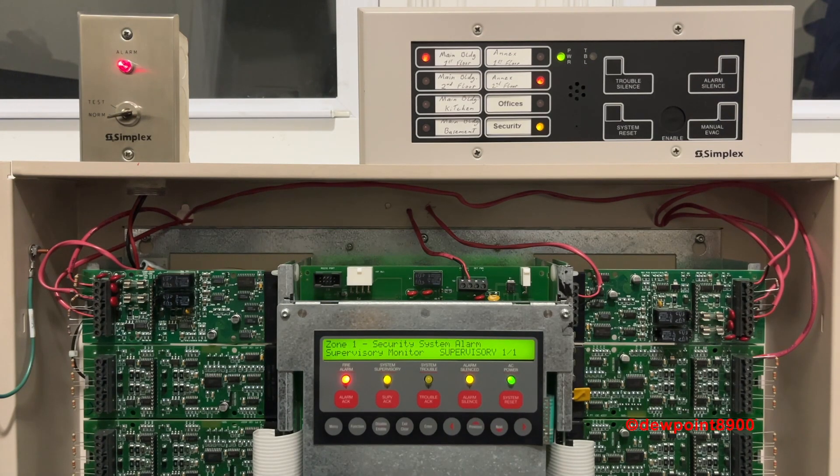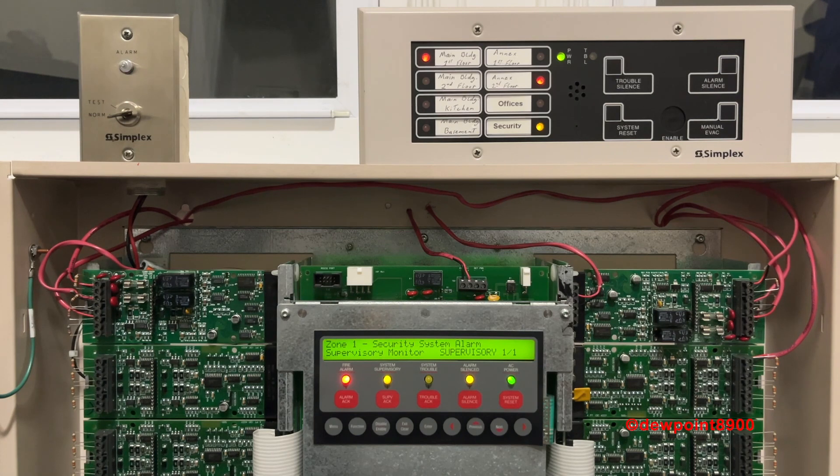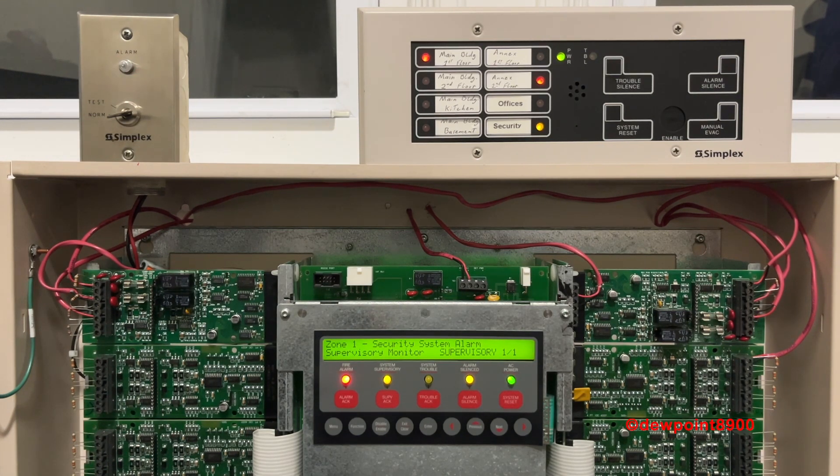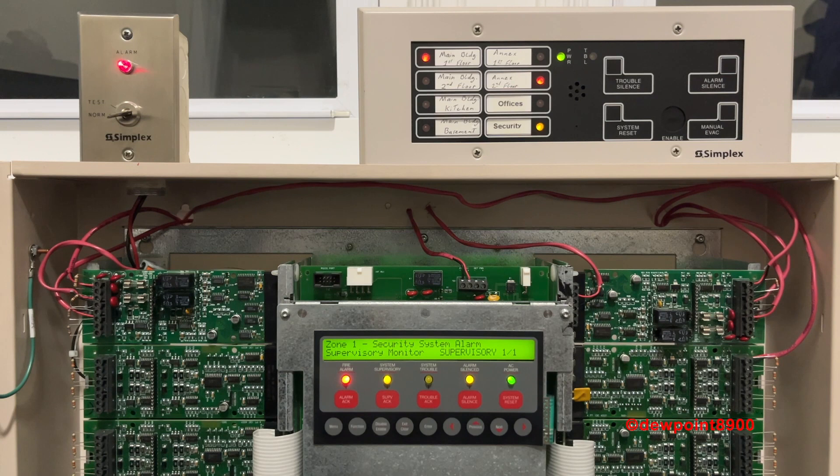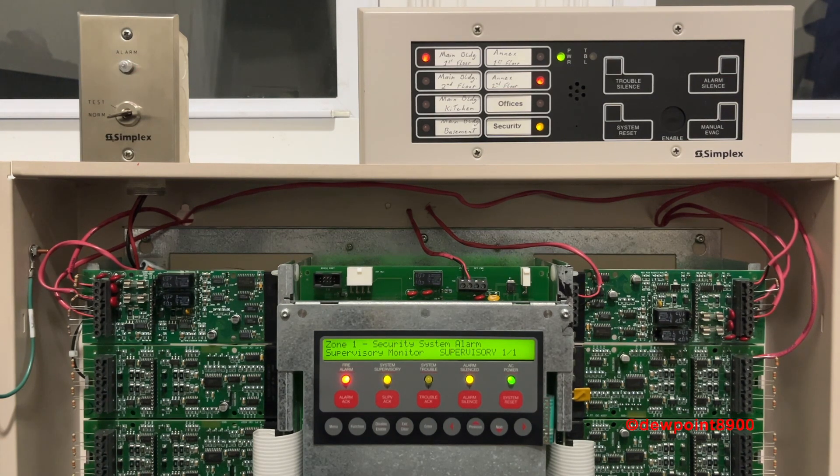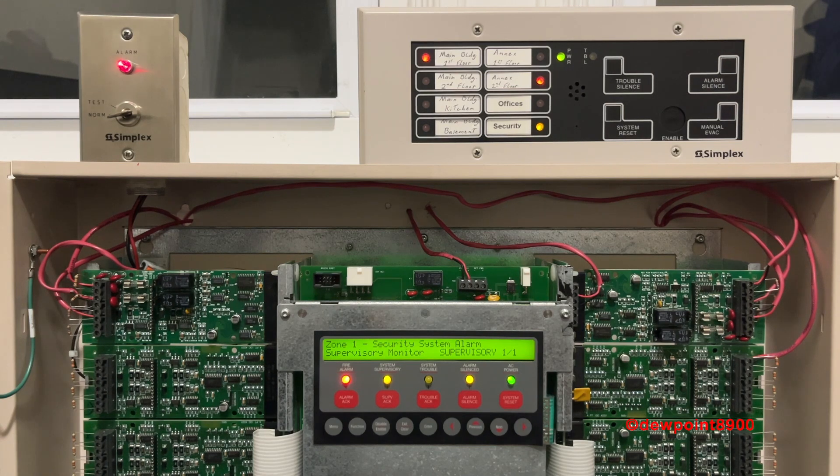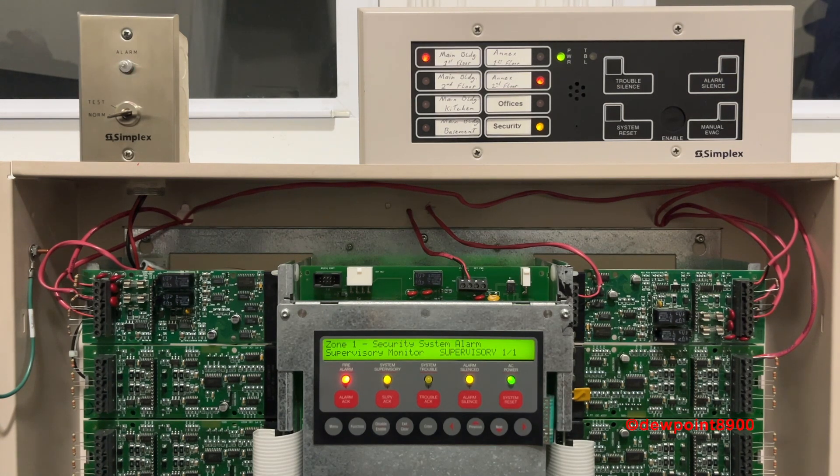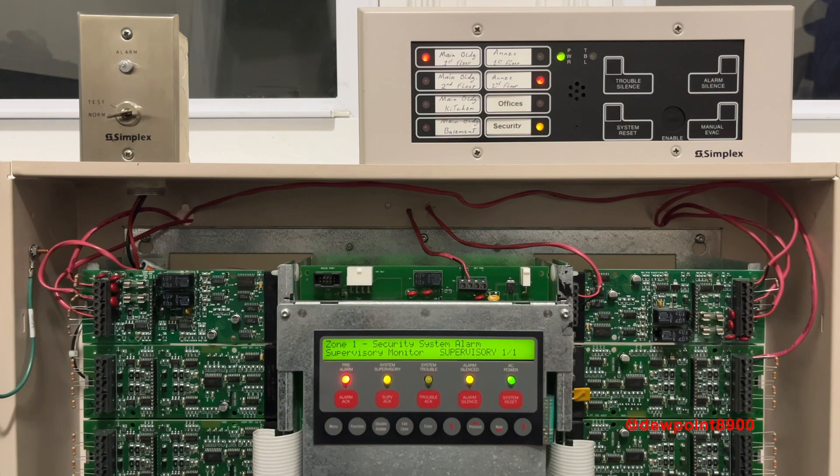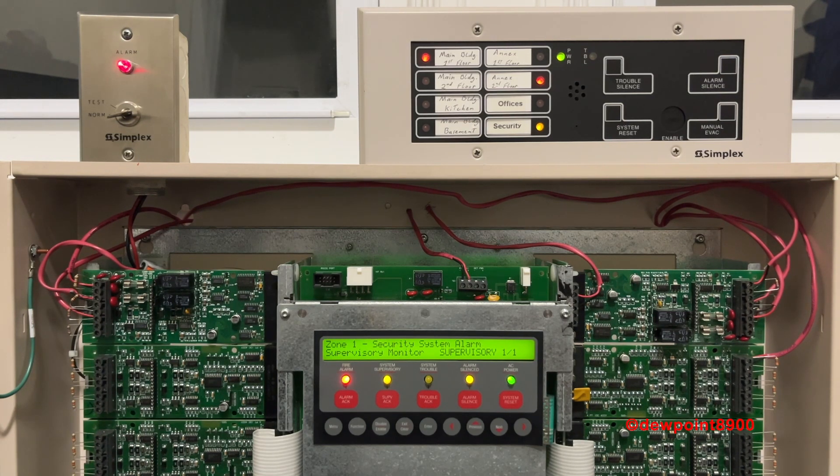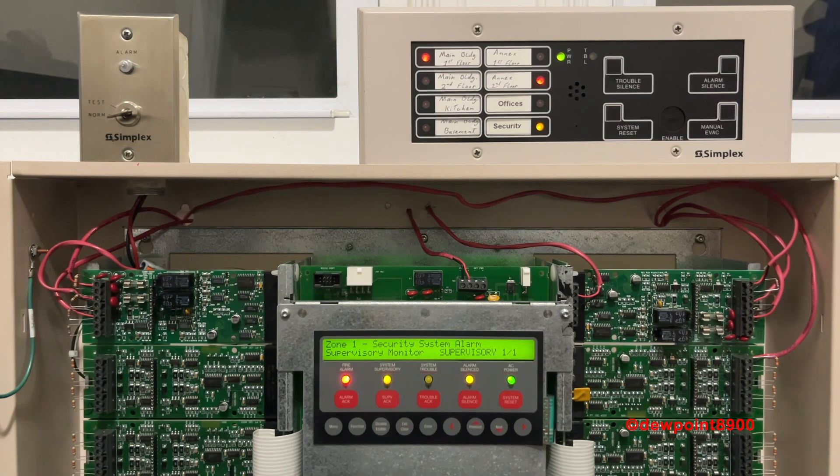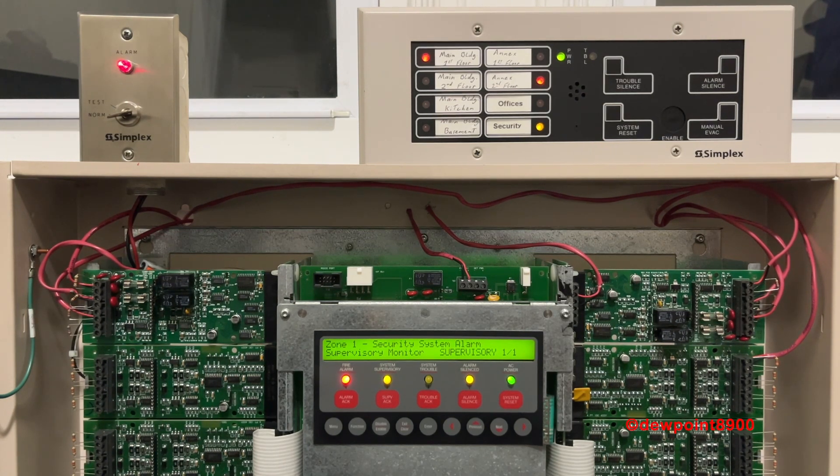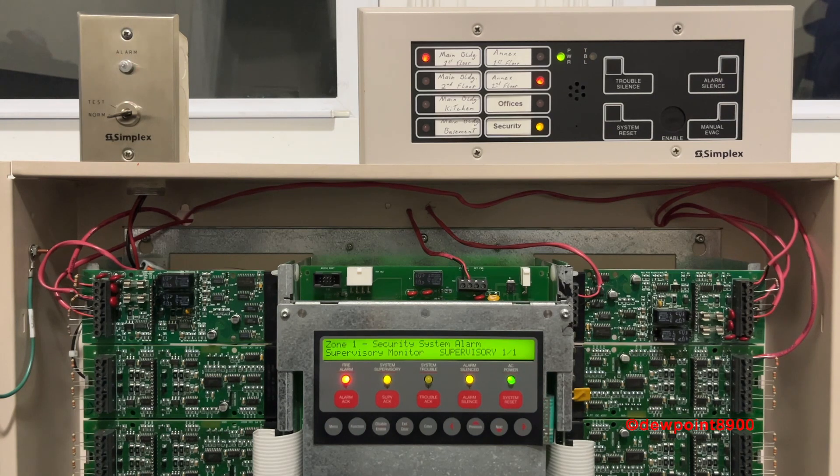Like most modern Simplex panels, a system reset takes a while to clear, although the 4005 is particularly notable for its long delay. While we wait for the reset to finish, it should be noted that the 4005 and other panels from this time period and beyond will abort the system reset if a device is still in an alarm. The 4005 is also capable of resounding signals if the same zone is activated again in a subsequent alarm. These are features that older panels like the 4002 do not have.